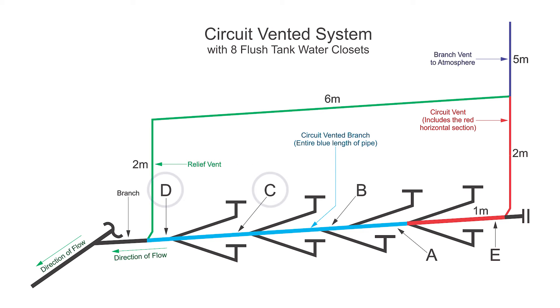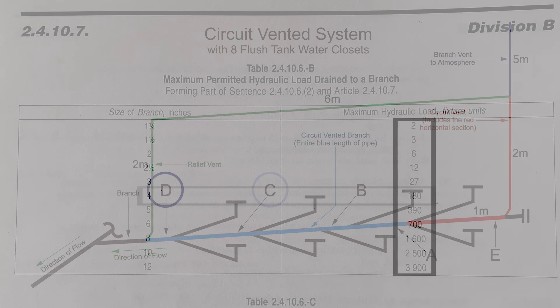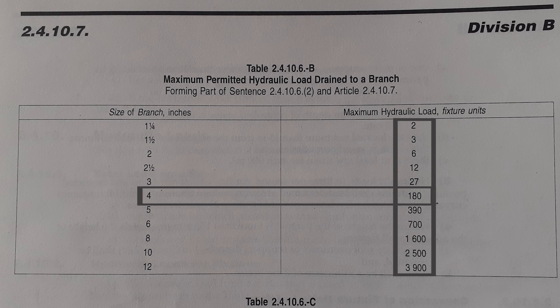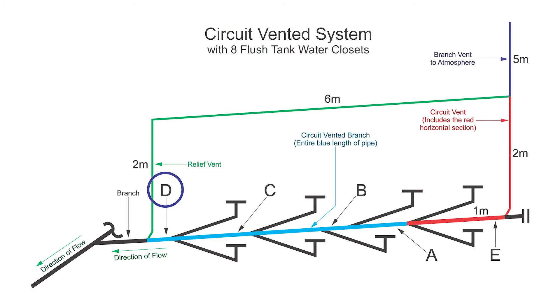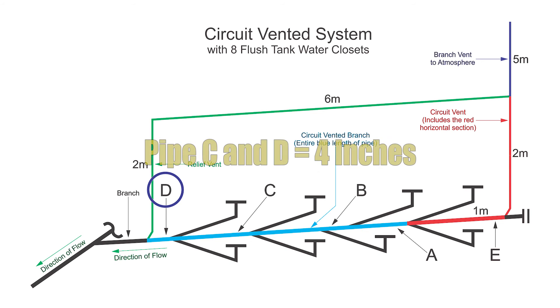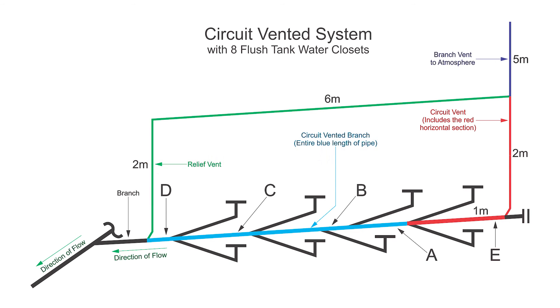For pipes C and D, let's look at our branch table. We're already at 4 inches and we can't go smaller — we can handle 180 fixture units on 4-inch pipe. At pipe D we have only 32 fixture units, so we're going to be 4 inches for the rest of the way.